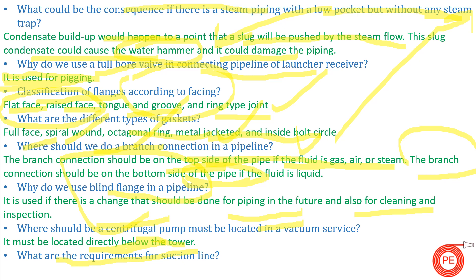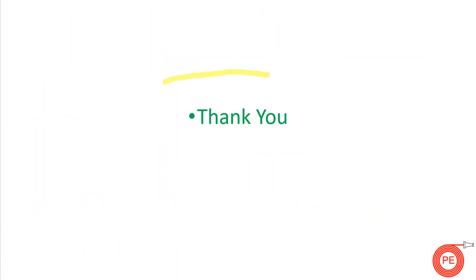Last question: what are the requirements of a suction line? For a suction line you should have a reducer — tell me in the comments which type of reducer is used in a suction line versus a discharge line. You also need a strainer, a block valve, no pockets, and proper straight length.